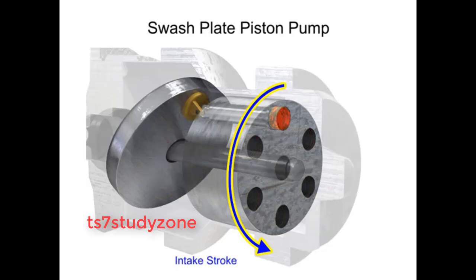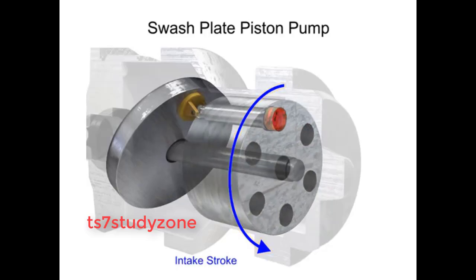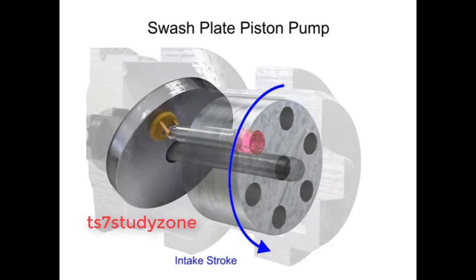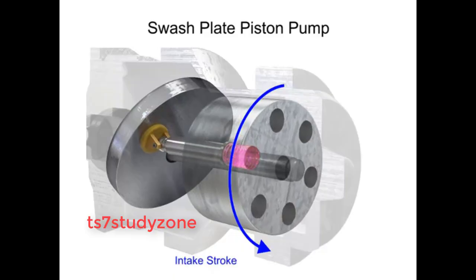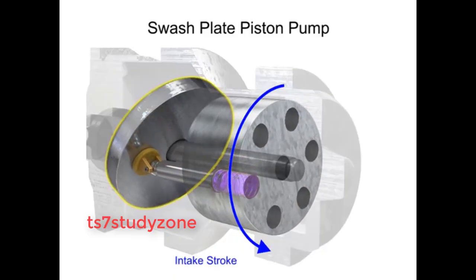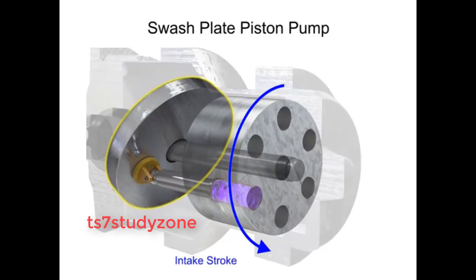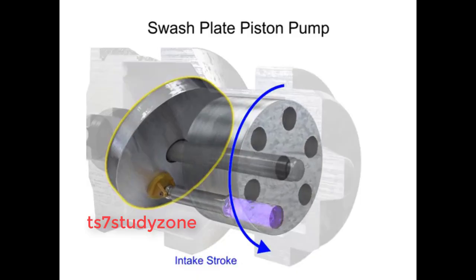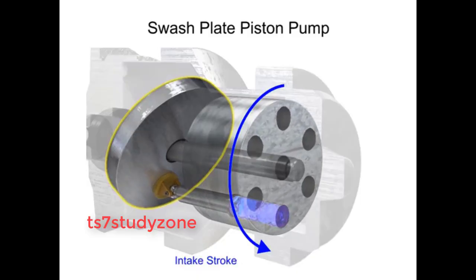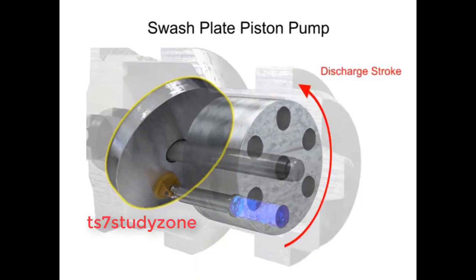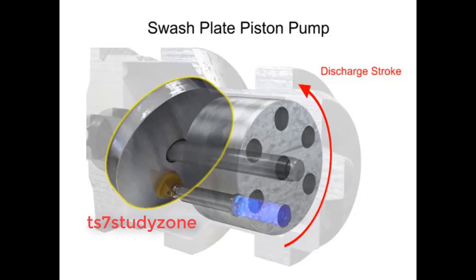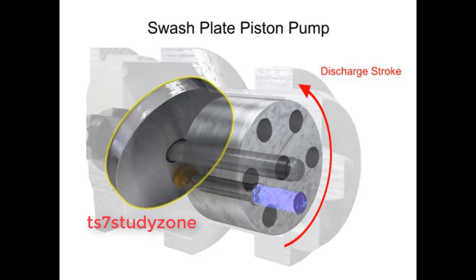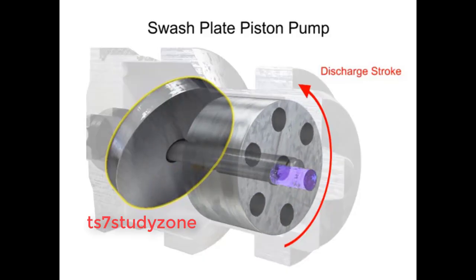On the intake stroke, a spring ensures the pistons pull back and maintain contact with the swashplate, causing fluid to fill the empty cavity left behind. On the discharge stroke, the angle of the swashplate forces the pistons back inside the piston block and discharges the fluid.